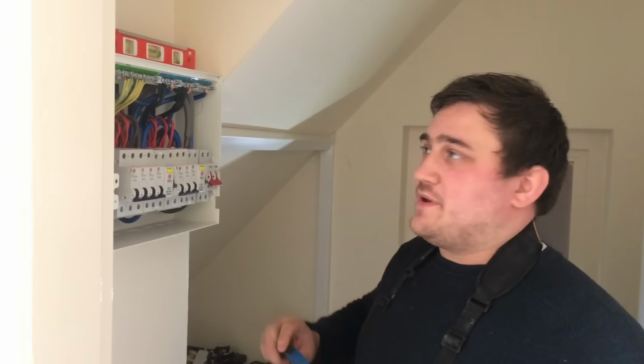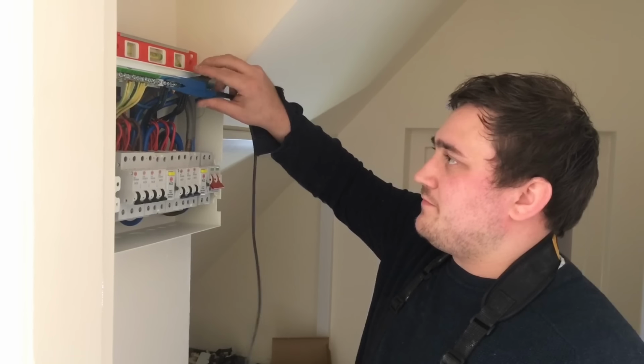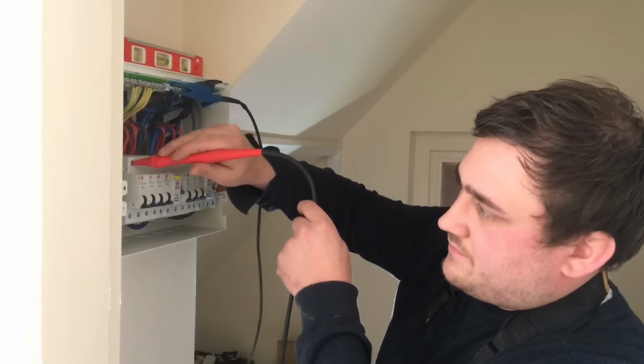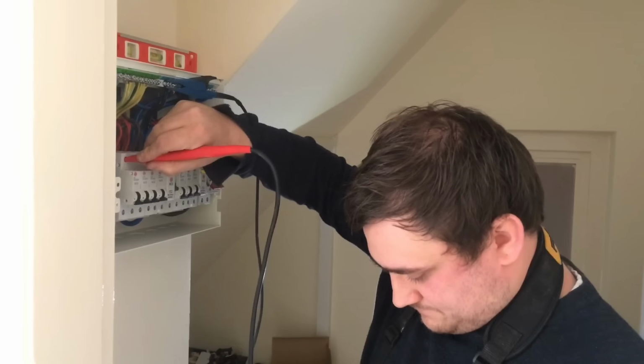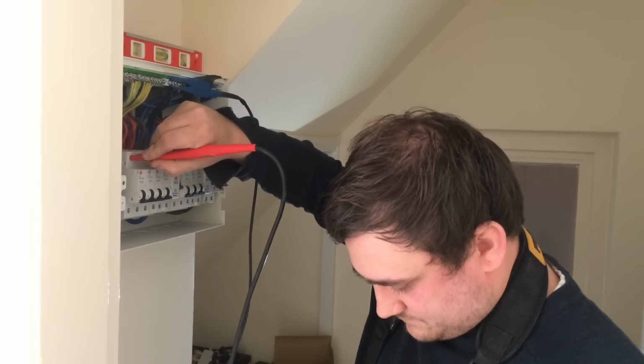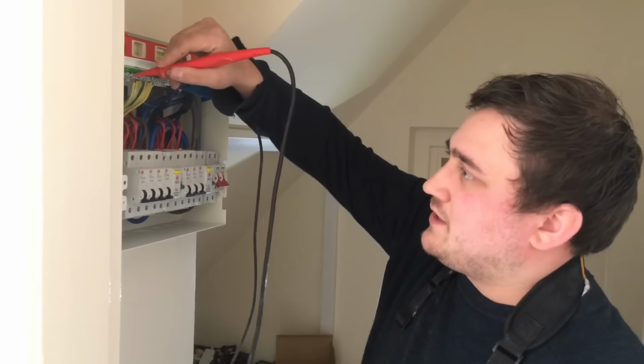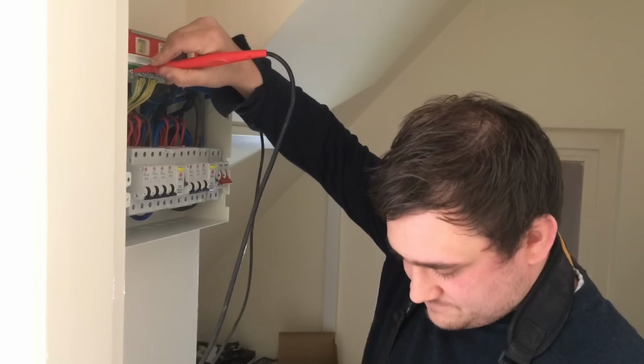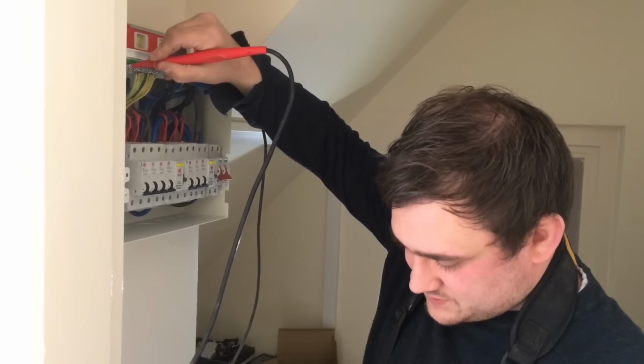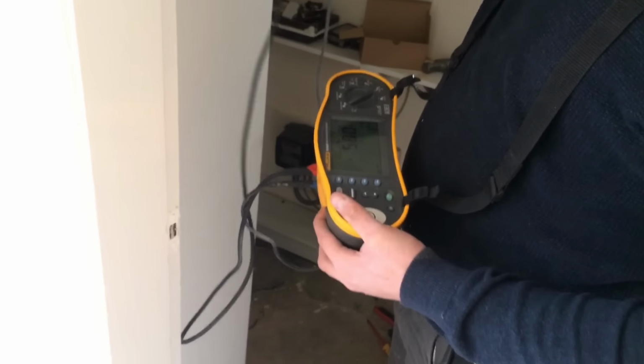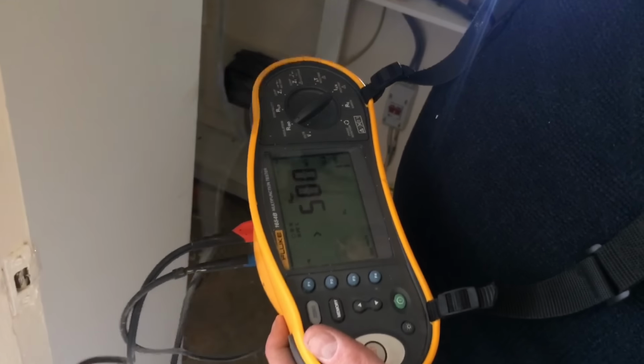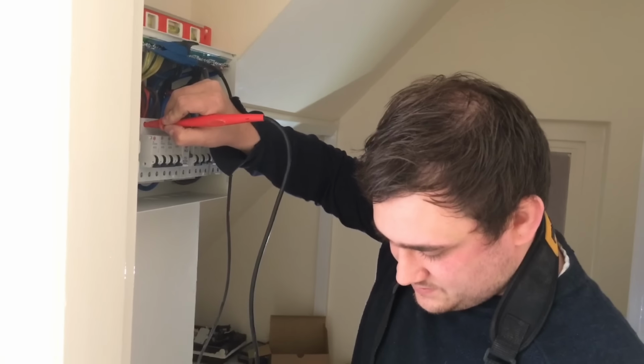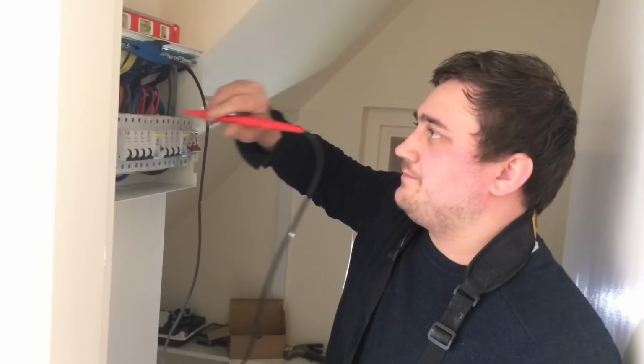We're going to do the same combination, we're going to go between neutral and line. Yep. I'm going to go between neutral bar and earth while we clamp it on, 500 megaohms. Now we're going to go between the earth bar and the line, and again 500 megaohms. That concludes our insulation resistance test.